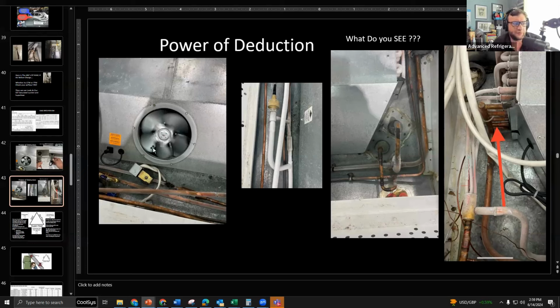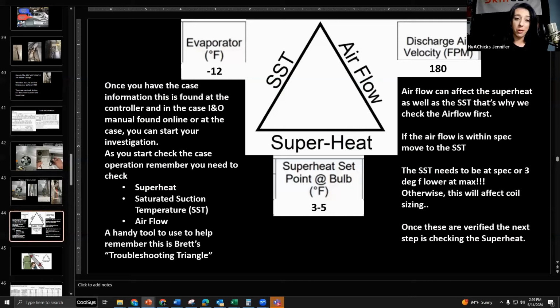And it was because the fan was moving so much air across, it was causing the expansion valve to open up as wide as it could just to funnel as much refrigerant through as possible. In essence, it loaded that little 5/8 line up with too much refrigerant, which made too high of a pressure drop because it wasn't made for that quantity of refrigerant. This coil is only 2,900 BTUs. It was probably shoveling 3 times that amount through that same little suction pipe. And that's why it froze where it did, too. On those pictures, you can clearly see what's frozen and what's not, and that's why it did that.